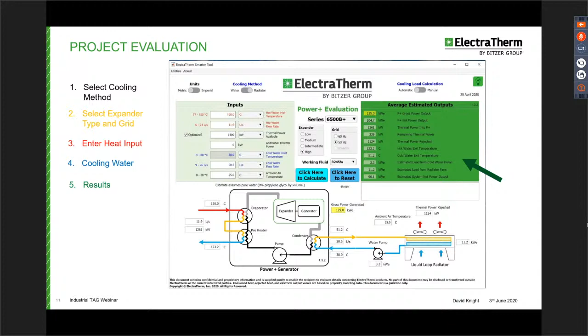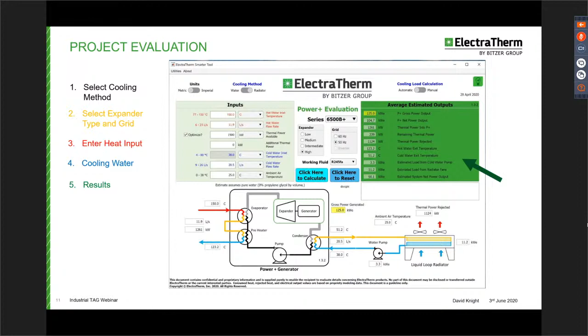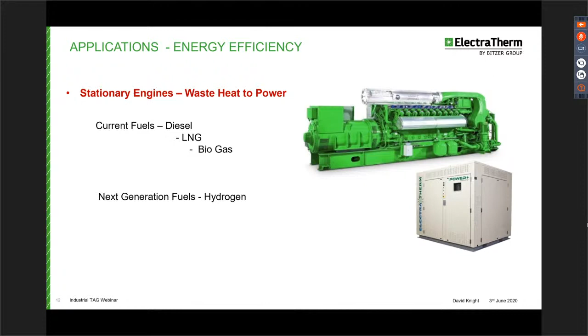We also do an economic assessment, and that uses 4 factors. We look at the value of electricity, the overall capital cost, the runtime of the plant, and the output from the PowerPlus generator. And that will calculate a return on investment and also a simple payback. So our applications, as I said, are many and varied. The primary application is stationary engines. So we take the waste heat to power from jacket water systems and also from the exhaust systems. It doesn't matter if you're using current fuel such as diesel, LNG, or biogas, or you're looking at the next generation fuel, which is hydrogen. There will be heat, and you'll need to improve your efficiency, and we can do that with the PowerPlus generator. And that's particularly important with hydrogen because hydrogen will be more expensive. You need more bang for your buck.